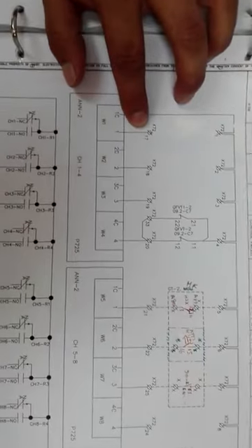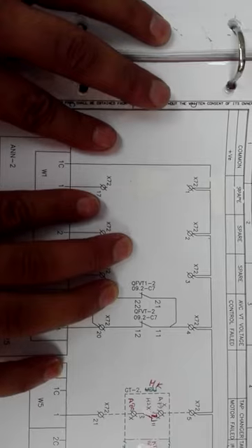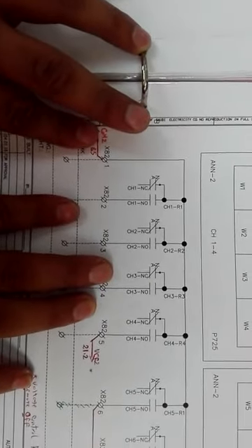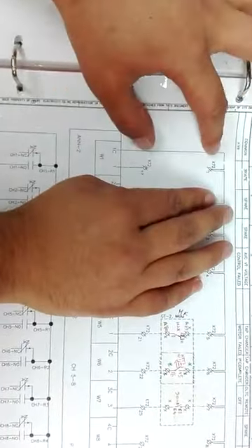Now for the timing test, what we need to check is the timer for channel 1 or window 1. Simply we need to start the timer for this, because this is our input, this is our output. So we will set our timer like this. We will make the connection from start to stop. How much time it takes, it will automatically stop.